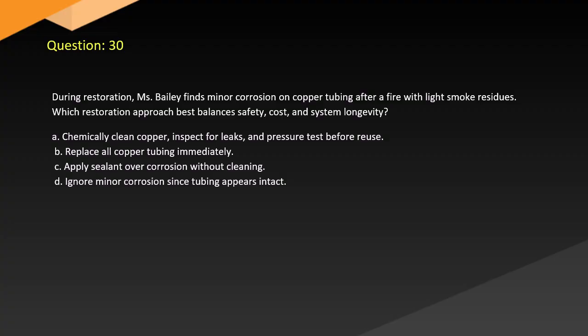Question 30. During restoration, Bailey finds minor corrosion on copper tubing after a fire with light smoke residues. Which restoration approach best balances safety, cost, and system longevity? A. Chemically clean copper, inspect for leaks, and pressure test before reuse. B. Replace all copper tubing immediately. C. Apply sealant over corrosion without cleaning. D. Ignore minor corrosion since tubing appears intact.